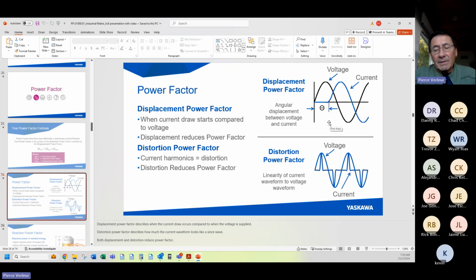And as I mentioned before, when the matrix drive goes into eco mode and basically acts as a contactor, it only goes into eco mode when the motor's at full speed, full load. Therefore, the displacement power factor is not bad, because the current doesn't lag the voltage very much when the motor's going full speed, full load. The distortion power factor is that gate valve that I talked about in the pipe. That gate valve's the VFD, and it causes all kinds of distortion, so much so that we can significantly reduce the power factor.